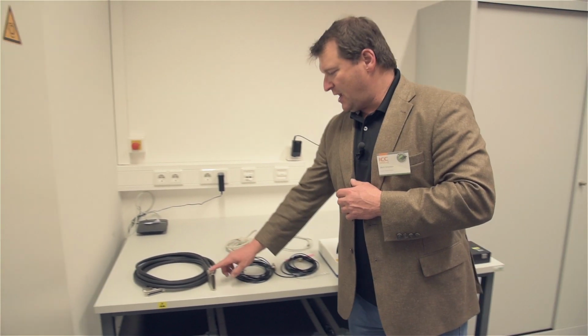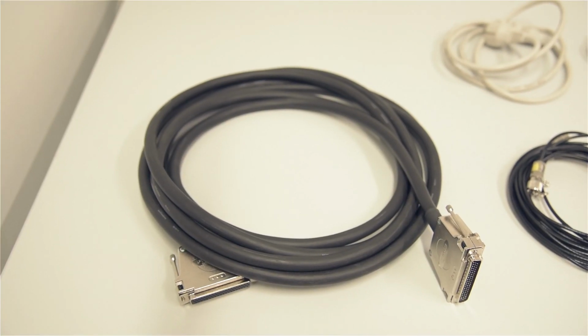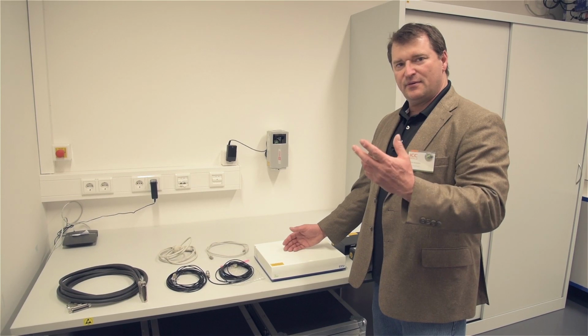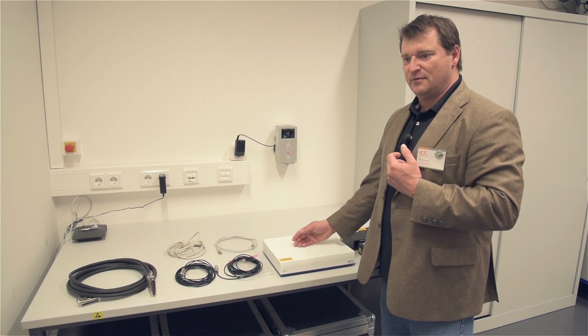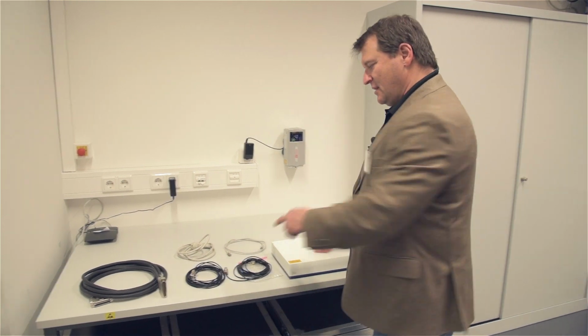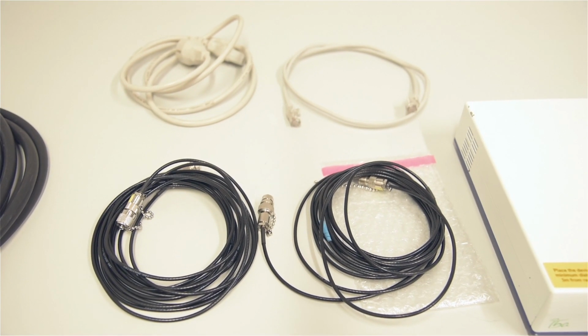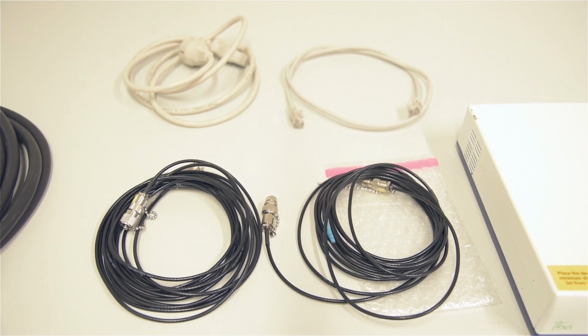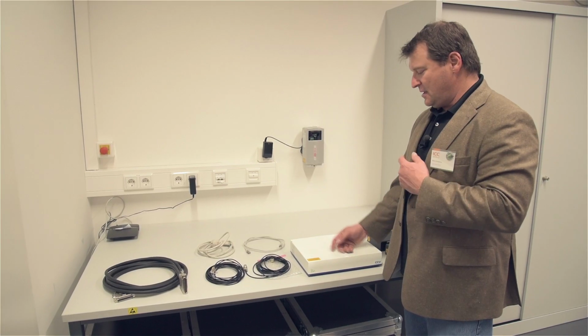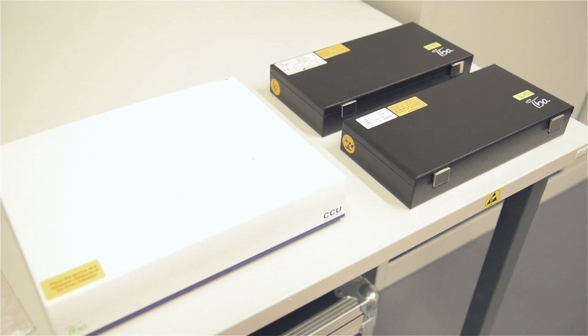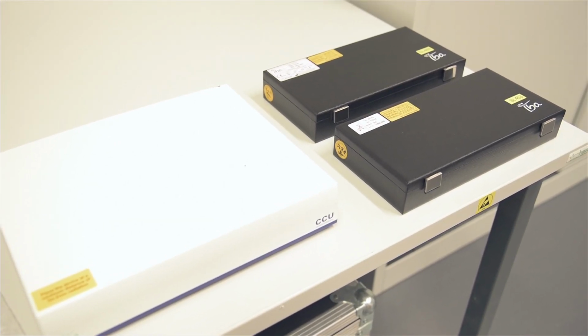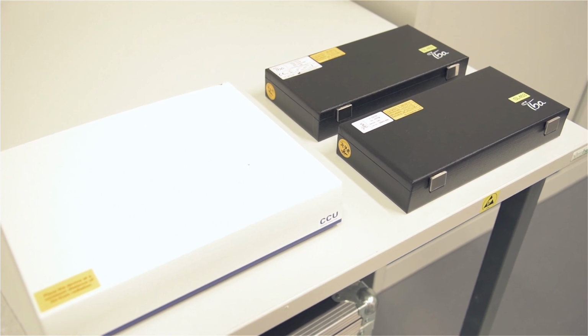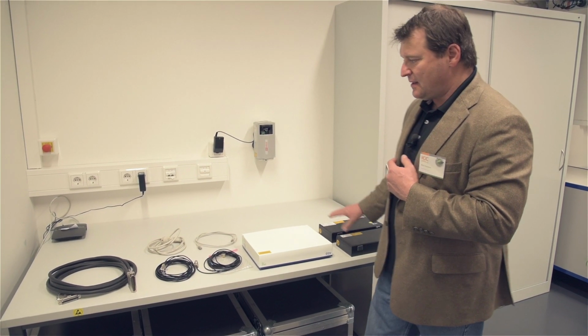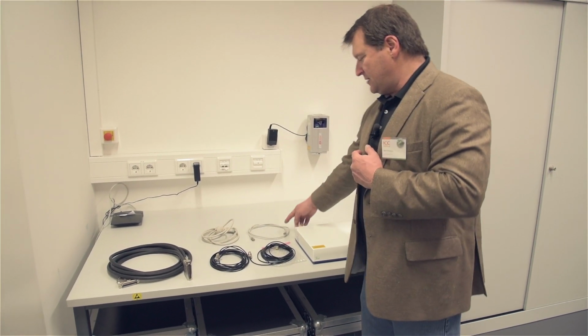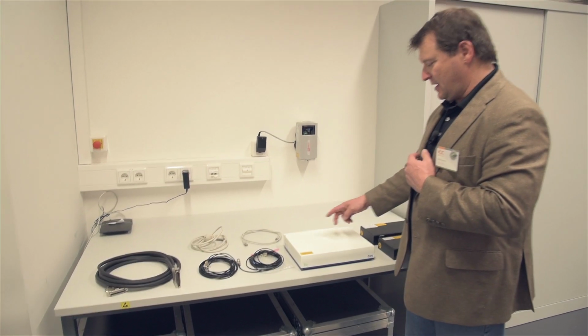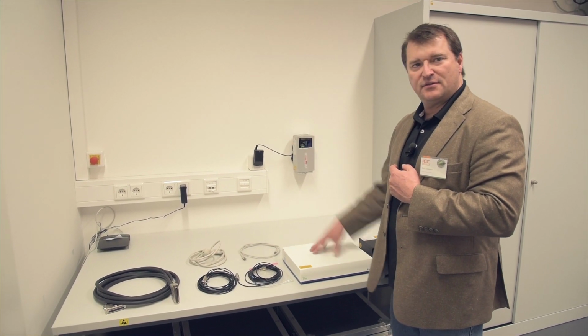We have the communication and power cable that goes from the CCU to the tank body. It allows power to the rails. It allows communication back to the CCU of coordinates, locations, etc. We have our 2 triaxial cables for communicating signal from the detectors back to the CCU. We have the CCU here. Our 2 detectors, in this case they're ion chambers, CC13. This is what we're going to start with, our 2 for a reference detector and a field detector. Power cable for the CCU and a standard Cat5 Ethernet cable to facilitate communication from the CCU out to the software.